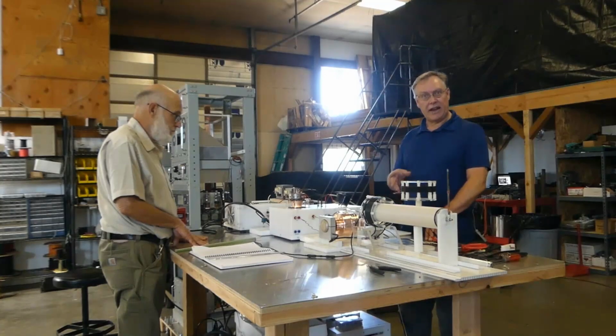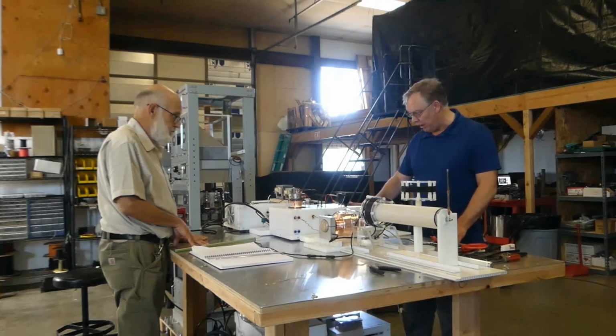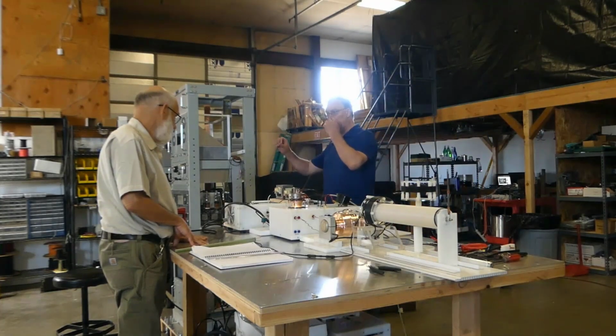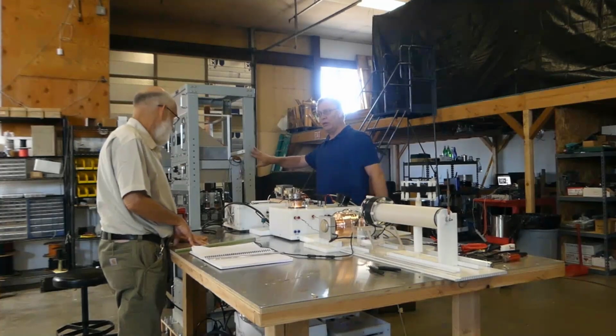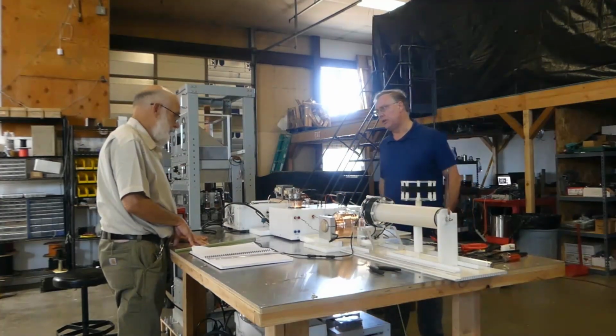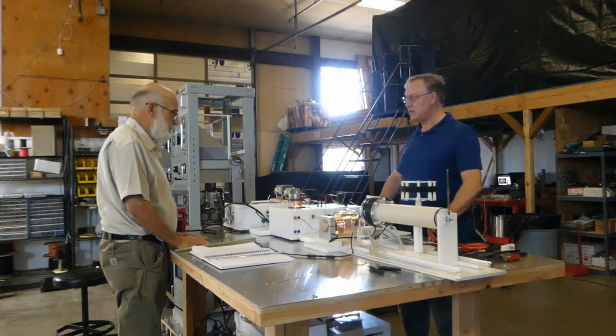I'll just add a bit on that, because when we didn't have that and we were connecting back to the generator ground, I believe, Eric, you were able to put a fluorescent bulb on the chassis, and it actually lit up. What's the reason it lights up? Because this thing is designed to transmit into the earth. So it's basically transmitting lots and lots of RF.